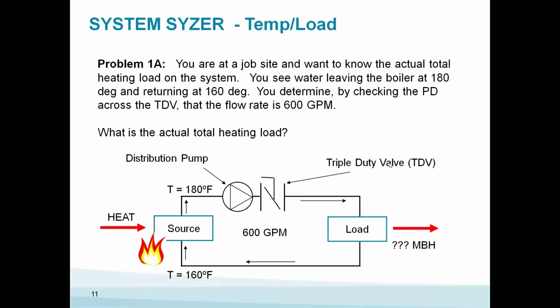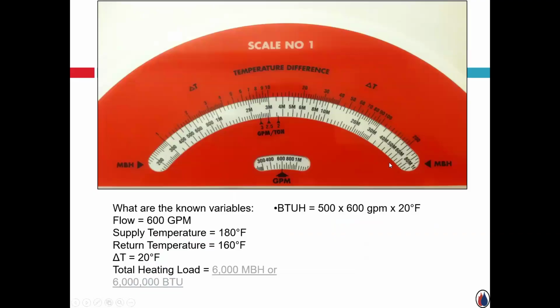And so all we're doing is taking that. I mean, first of all, it's just math. We can figure it out. But if you take the scale, you kind of work backwards. We're not trying to find out the GPM. We already know it. We figured it out looking at the triple duty valve. We said, hey, we got a flow rate of 600 gallons a minute. So I'm going to line up that wheel right at 600.